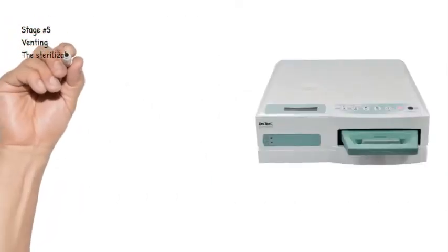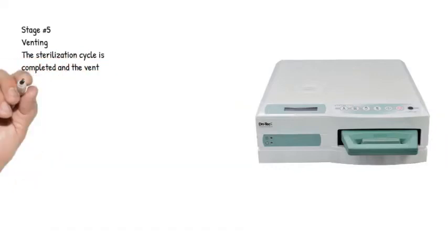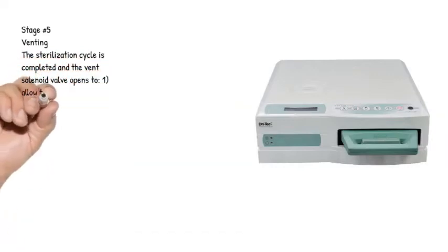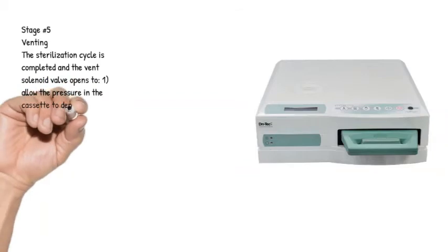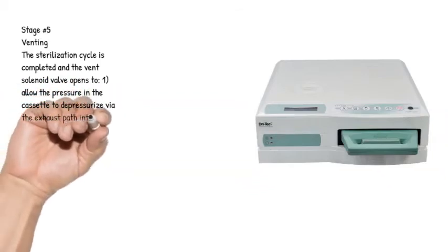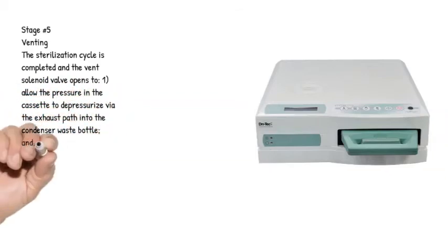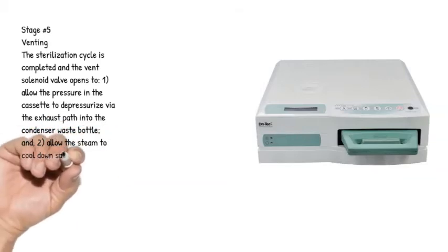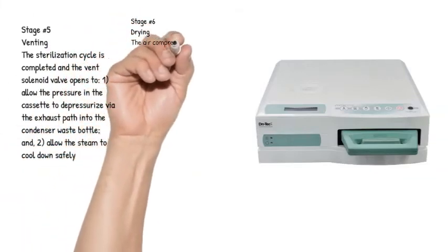Stage number 5. Venting. The sterilization cycle is completed and the vent solenoid valve opens to 1. Allow the pressure in the cassette to depressurize via the exhaust path into the condenser waste bottle, and 2. Allow the steam to cool down safely.